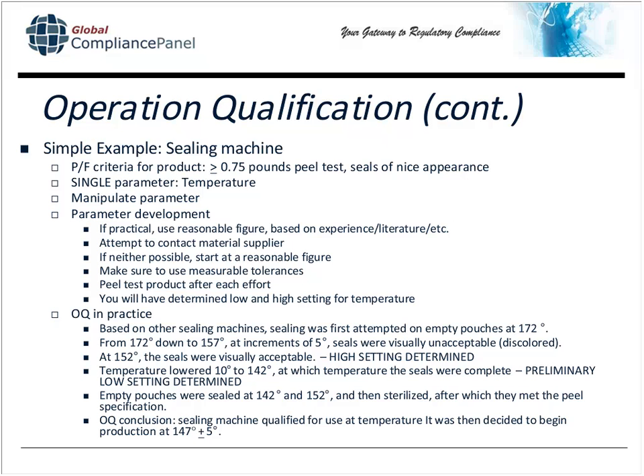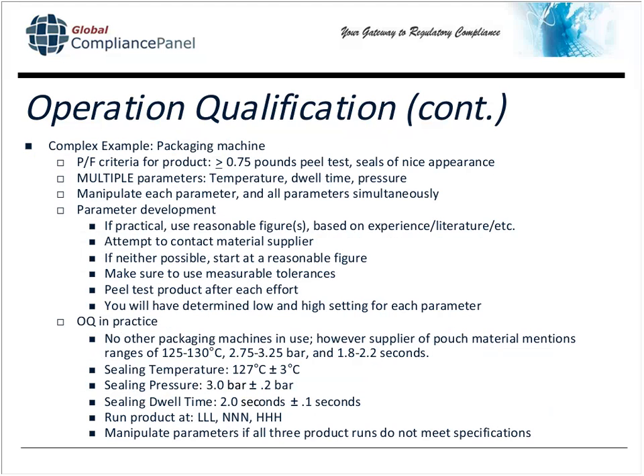What this OQ in practice leaves out, not by design, I apologize, is going down to the temperature at which pouches fail and increasing that a bit. So continuing this, let's say that the empty pouches at 132 degrees did not seal. We're going to continue to increase that to 133, 134, 135, until we find a temperature at which the pouches do seal, and that's my minimum setting. So at the end of the OQ, much like the IQ, you're going to have a conclusion. And at this point, we're going to decide to begin production at the nominal plus and minus the tolerances that we had in place.